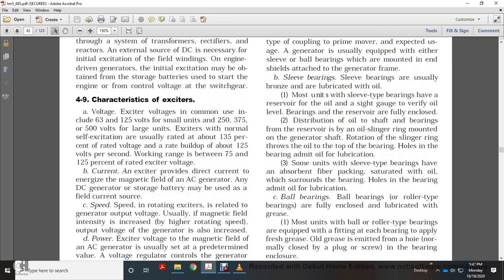All right, 4-9, character for the excited voltage. The common exciter voltages are 63 to 125 volts, and for small units 250, 375, 500 volts. Larger units excited with normal self-excitation are usually rated at 135% of the rated voltage, with a build up of 125 volts per second. The working range is between 75 and 125 percent of the rated exciter voltage. Currently, the exciter provides the direct current with the energy of the magnetic field of the AC generator.